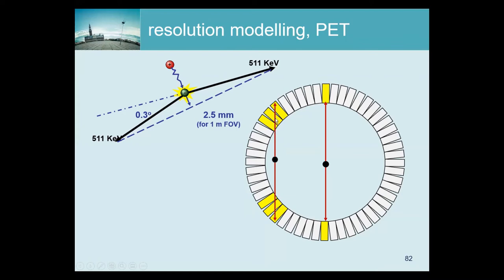But here, closer to the edge of the field of view, this point source can send photons into this crystal, but if they don't attenuate, then they can propagate into the next crystal. These crystals are very long but very thin. So crossing that crystal just a few millimeters is not that difficult. So it can hit any of those crystals. And if it does that, and since we don't know where in the crystal the scintillation took place, that creates a lot of possible LORs. So here, for example, it scintillates in the bottom of this crystal. We don't know where it scintillates. So we use the typical expected scintillation depth, which is like three millimeter crystals would be less than a centimeter. So we put them always there. And as a result, we have all these LORs that are actually activated just by this photon. And that means we have a much larger cone. This is a reason to make sure that the patient is in the center of the scanner and not at the edge.